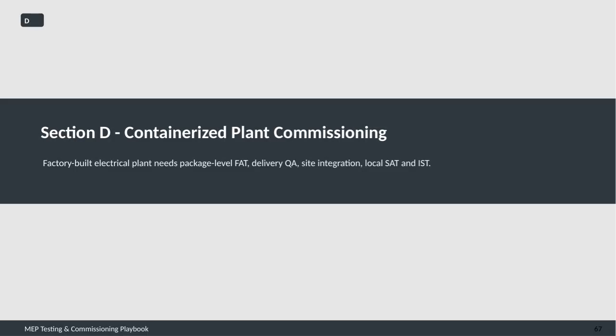Now, let's focus on Section D, which covers containerized plant commissioning. This involves several key stages to ensure the factory-built electrical plant is ready for operation. First, package-level factory acceptance testing, or FAT, is performed to verify that the plant meets all design and performance specifications before it leaves a factory.